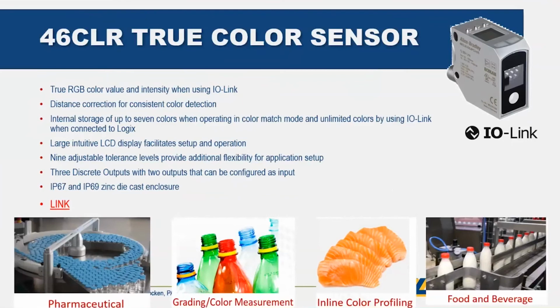It has a distance correction for consistent color detection. Anybody that's used a color sensor knows they are so sensitive to the distance to the object. But with this correction factor, when you use IO-Link, it makes it a lot easier to sense your distance from the color that you're sensing.